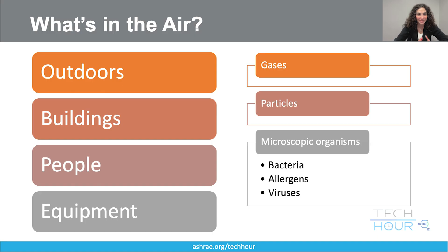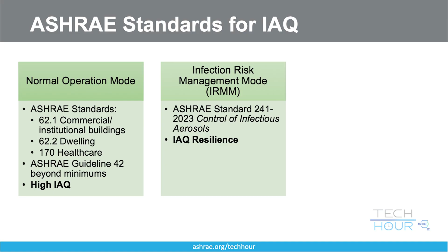Now, ASHRAE provides the backbone of indoor air quality standards and guidelines in buildings. Today I'm going to focus on ASHRAE Standard 62.1, the most prominent ventilation standard, which applies to commercial and institutional buildings—not to be confused with 62.2, for dwellings, and ASHRAE Standard 170, for healthcare. The second is ASHRAE Standard 241, the new standard for control of infectious aerosols, published in 2023. And finally, ASHRAE Guideline 44, which provides strategy to deal with wildfire smoke, published in 2024. And I forgot one, Guideline 42, published in 2023, which provides beyond-minimum strategies beyond ASHRAE Standard 62.1. These standards, applied together depending on the situation, represent a major evolution in indoor air quality thinking.